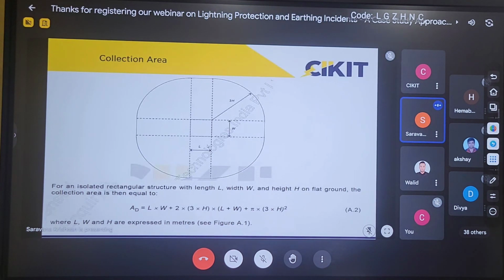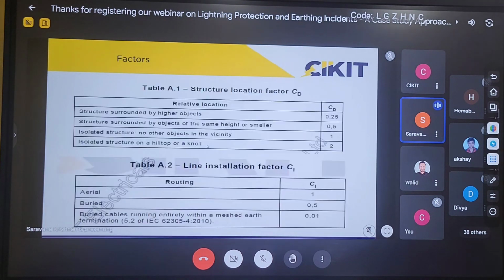The other parameters involved in calculating the risk, after the number of dangerous events, is the structure location factor. As I mentioned, if my building is surrounded by buildings which are much taller, then the risk due to lightning on my particular building will be lower. So if my structure is surrounded by higher objects, then the risk value will be lower. That is determined by the value 0.25.